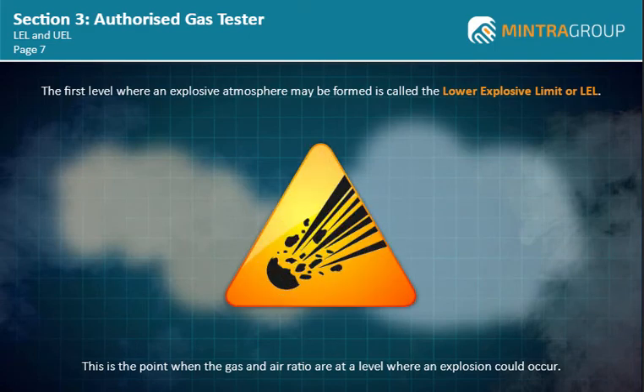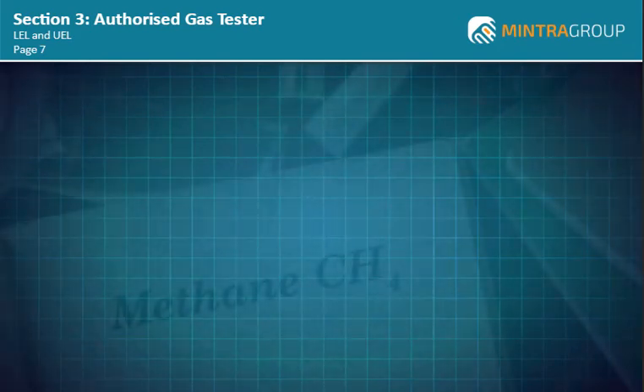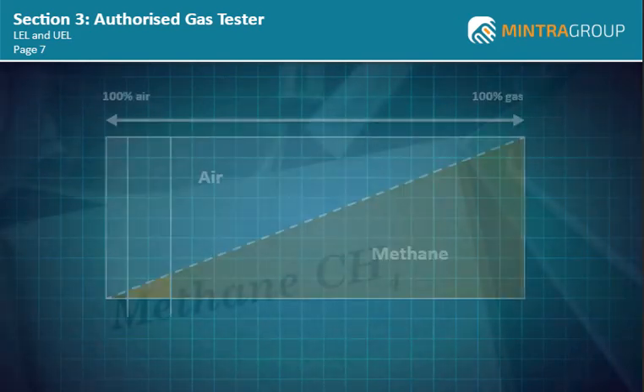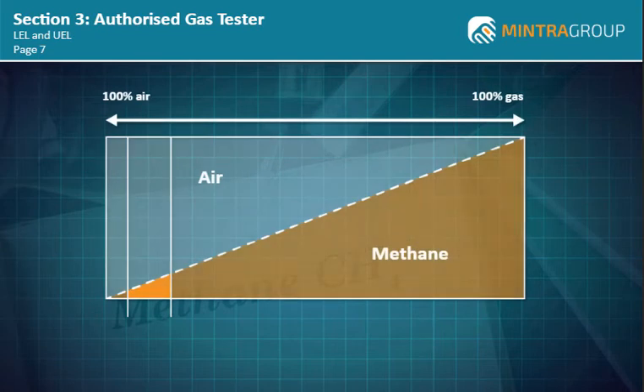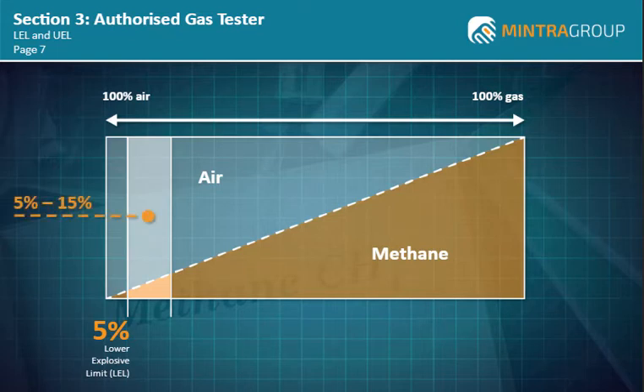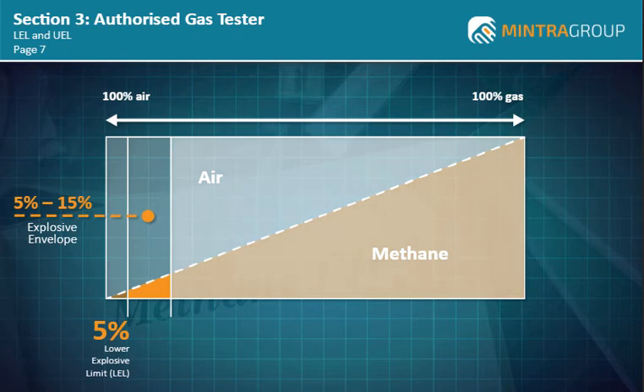Let's consider methane, one of the most common hydrocarbon gases found in our industry. Only a small amount of methane is required in air before it reaches its LEL. 5% by volume of methane in air is its LEL. Any ratio of methane from 5% to 15% by volume in air will form an explosive atmosphere — this is called the explosive envelope. Any ratio above 15% by volume in air is deemed too rich to cause an explosion and is known as the Upper Explosive Limit, or UEL.